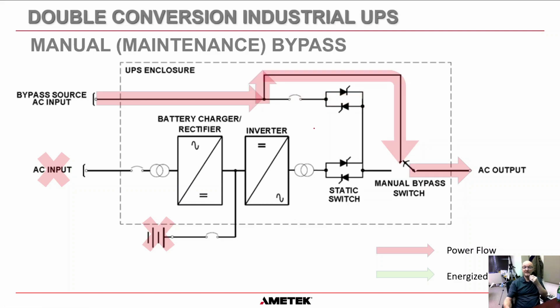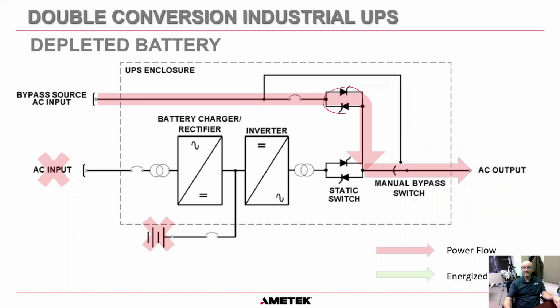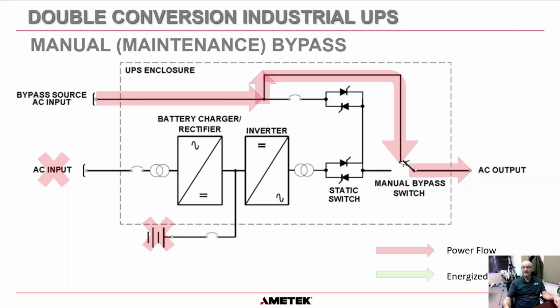And then last but not least, the difference between static bypass and manual bypass in this system. If you saw on that previous page, we were in static bypass going through the static switch. But now we're going to move this manual bypass switch to the bypass position. Okay? And in doing so, we make this connection here before we break that connection there. That's done internal within the switch itself. It's a make before break switch. And therefore you can follow the red there. That will be the power flow to the system. Okay?